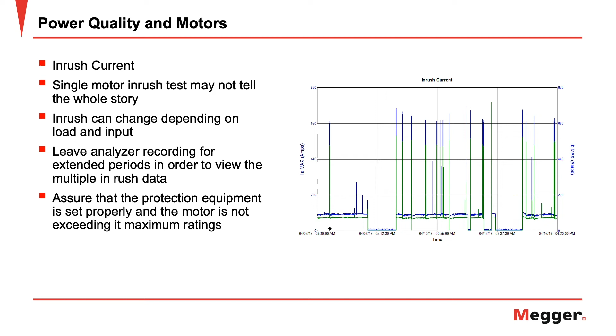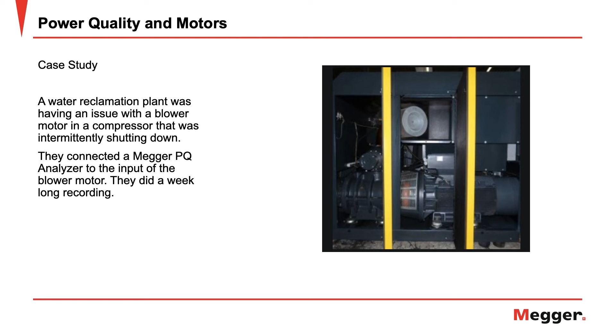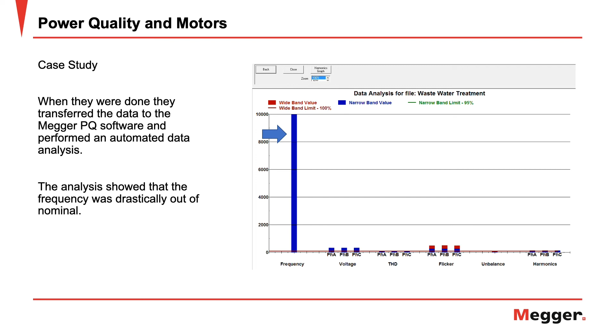A water reclamation plant was having an issue with a blower motor in a compressor that was intermittently shutting down. They connected the Megger PQ analyzer to the input of the blower motor, and they did a week-long recording. When the recording was completed, they transferred the data to the PC, and they performed an automated data analysis. The data analysis showed that the frequency was drastically out of nominal.